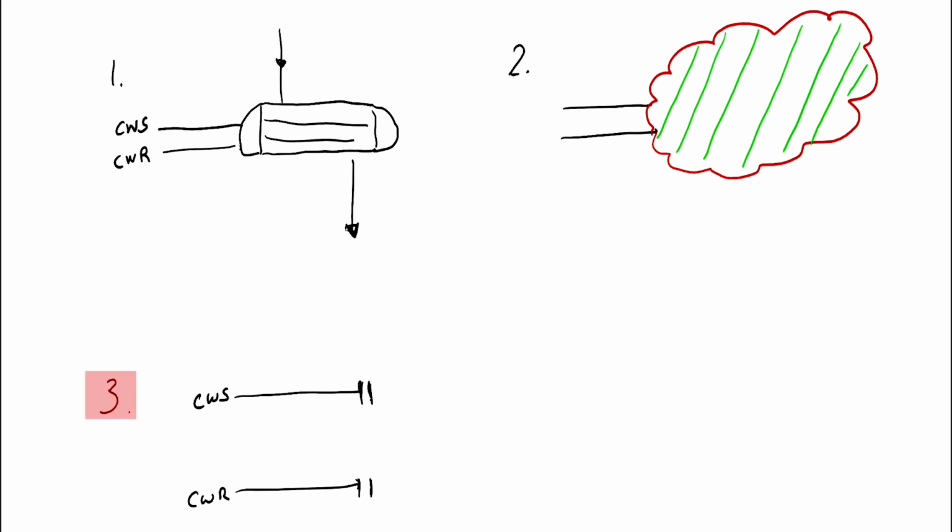Number three depicts what we're talking about. It looks like just two pieces of pipe, but let's indicate basically that cooling water supply and return. Now in the next revision, those pipes are still here with just caps and flanges. A good practice there is to carry this back to the original supply drawing and cap it there.